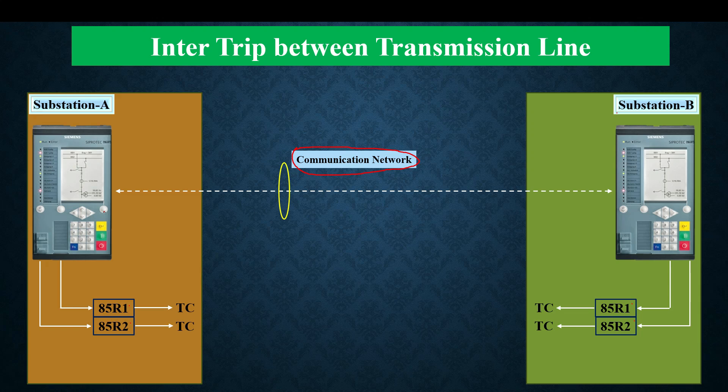The most important thing to know about inter trip is that on receiving an inter trip signal, the relay will not check any other condition. If substation A receives an inter trip from substation B, without seeing any condition it will directly operate either 85R1 or 85R2, and the circuit breaker will trip.